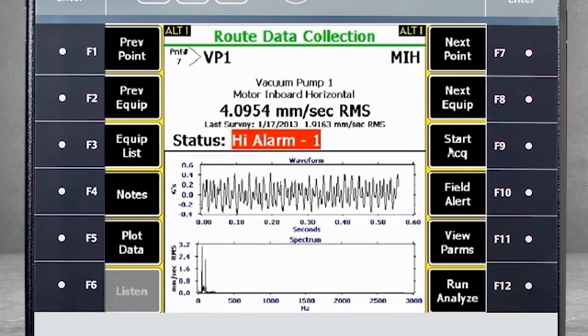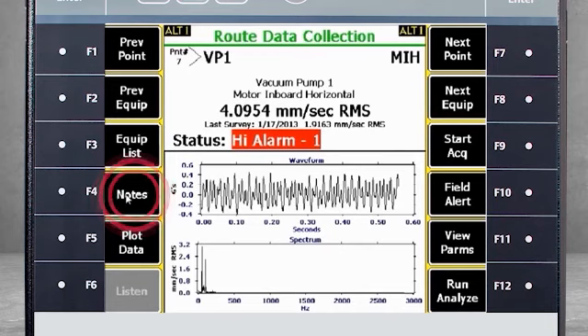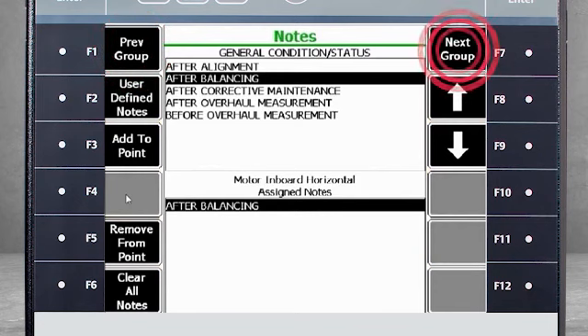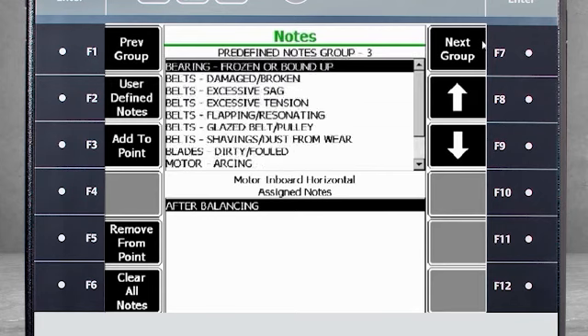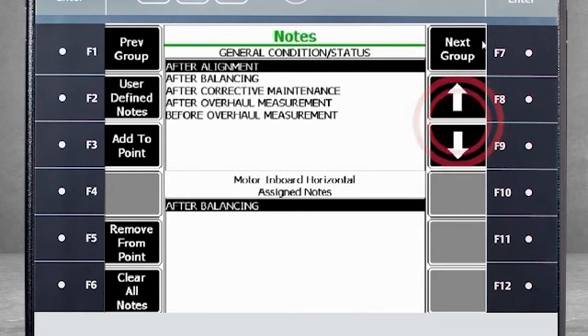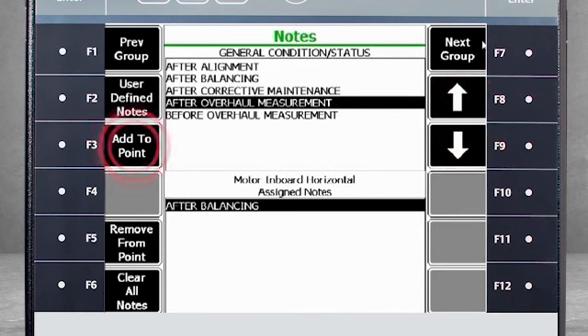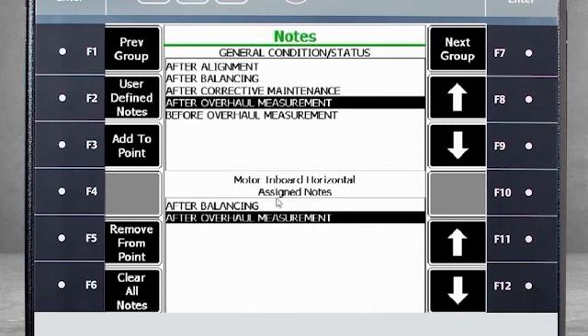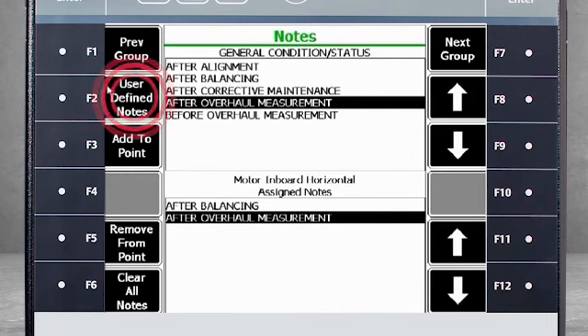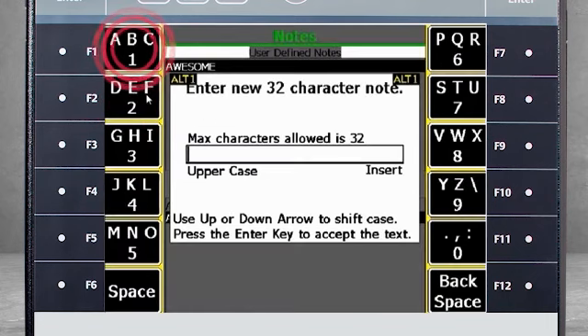F9 Start Acquisition and the Enter button on the analyzer will both start data collection. In the software, you can pre-configure groups of commonly used notes, which are then accessible from F4. F1 and F7 allow you to toggle between the groups of notes. F8 and F9 navigate between the notes, and F3 lets you add the highlighted note to the measurement point. Later, when collected data is downloaded in the software, the notes will also transfer. You can add several pre-defined notes quickly this way. But if you need to make a note that isn't in the list, you can add your own note in the field using F2 user-defined notes. Select F1 to add a note up to 32 characters.